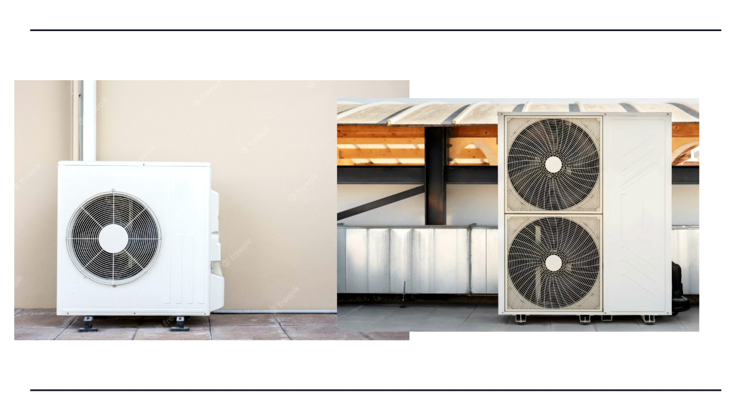So the one on the left has the inverter unit where it's just a single condenser fan, and its job is to pull air in from behind the unit and bring it out through the front of the fan unit. So basically it's sucking outdoor air through the heat exchanger and passing it out the front. The interesting thing with these is they take up a lot less room than the standard old air conditioning system of the past, and we can put them in places where they're a little tighter to deal with.